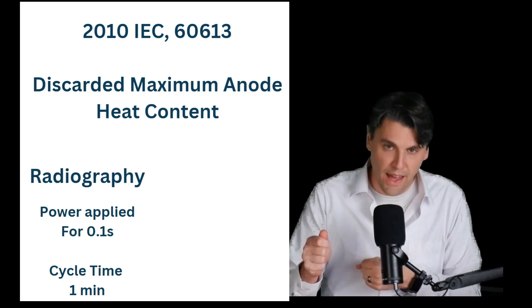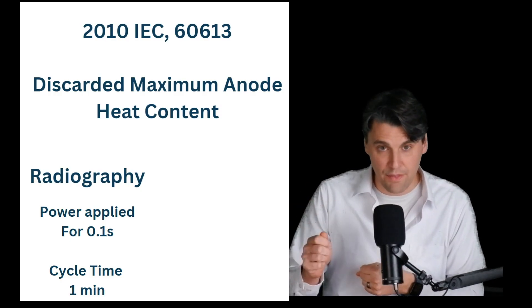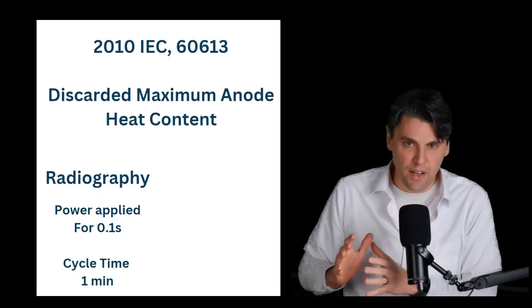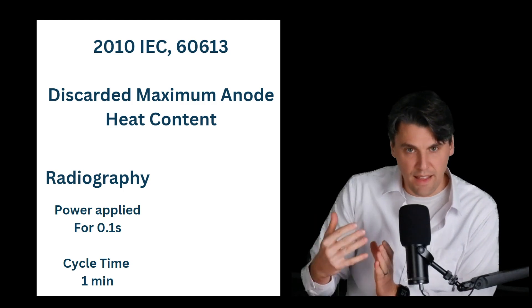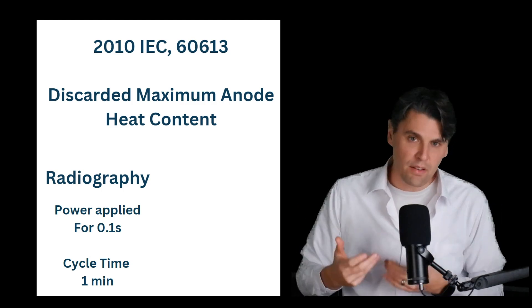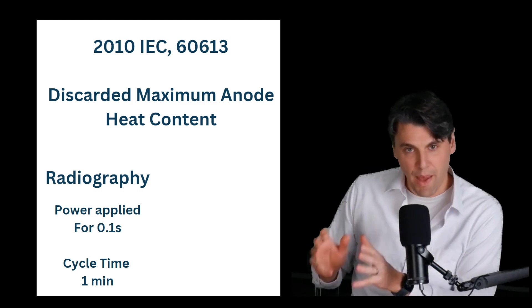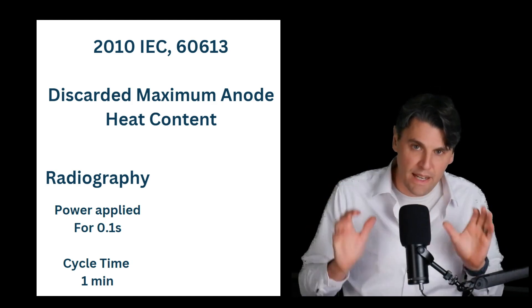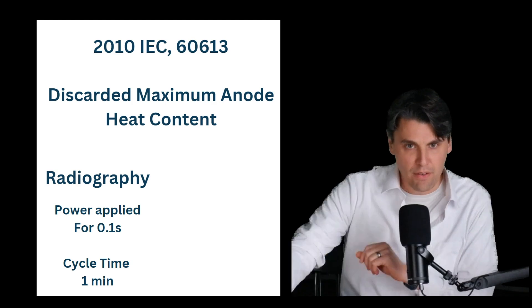Assume that you're going to turn that x-ray tube on for one-tenth of a second, then take the next x-ray in a minute. If you think about actually taking an x-ray, then the patient moves to another position, you take another x-ray, move again, take another x-ray. This type of clinical workflow — where you take an x-ray and the next one is a minute or more away — tells you the capacity of your tube to keep up with that kind of workflow. From a radiology perspective, this is found to be really useful.